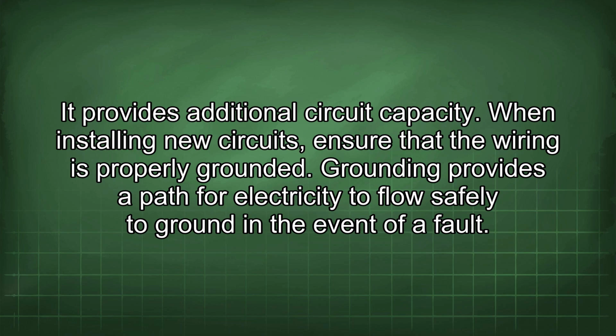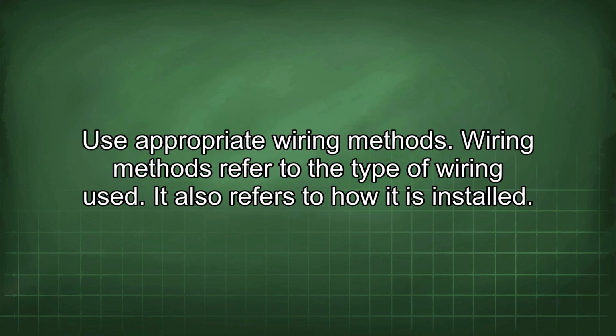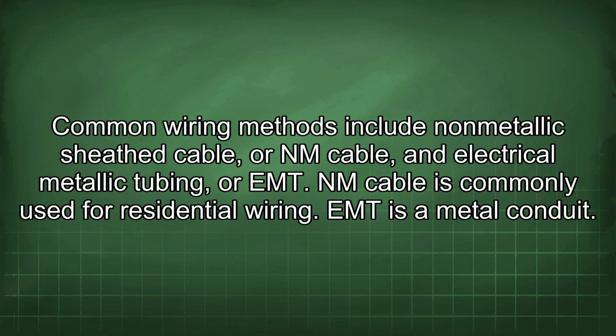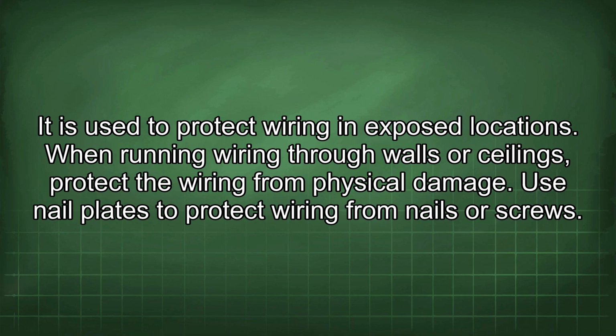When installing new circuits, ensure that the wiring is properly grounded. Grounding provides a path for electricity to flow safely to ground in the event of a fault. Use appropriate wiring methods. Wiring methods refer to the type of wiring used. It also refers to how it is installed. Common wiring methods include non-metallic sheath cable, or NM cable, and electrical metallic tubing, or EMT. NM cable is commonly used for residential wiring. EMT is a metal conduit. It is used to protect wiring in exposed locations.